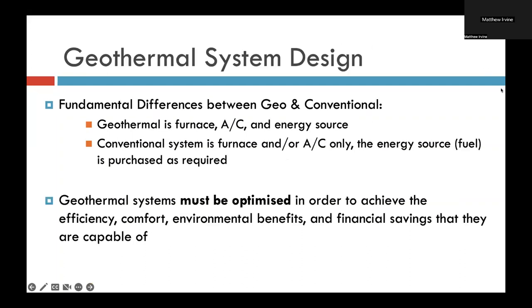The fundamental difference between a geothermal system and a conventional heating system is that geothermal is a furnace, an air conditioner, and an energy source, whereas a conventional system is simply a furnace and/or an air conditioner, but the energy source or fuel is purchased annually, monthly, as required for the life of the system. And then geothermal systems, because they are an energy source and because you have a heat exchanger buried outside, must be optimized in order to achieve the efficiency, comfort, environmental benefits, and financial savings that they are capable of.